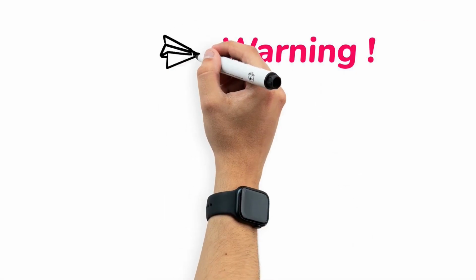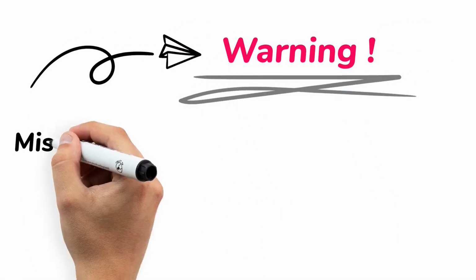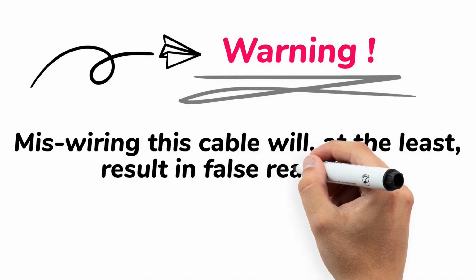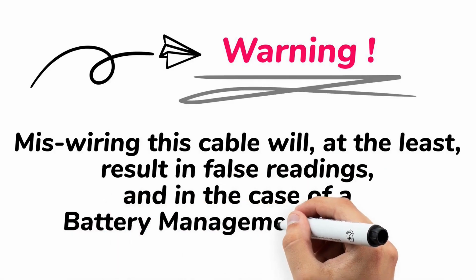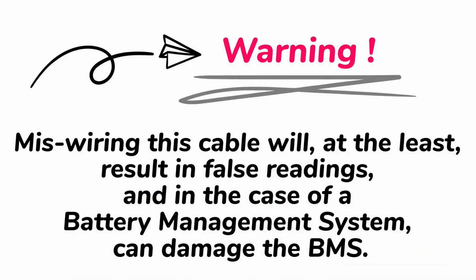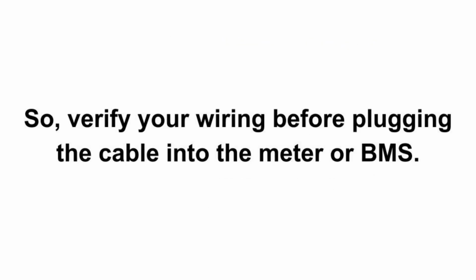Warning: miswiring this cable will, at the least, result in false readings, and in the case of a battery management system, can damage the BMS. So verify your wiring before plugging the cable into the meter or BMS.